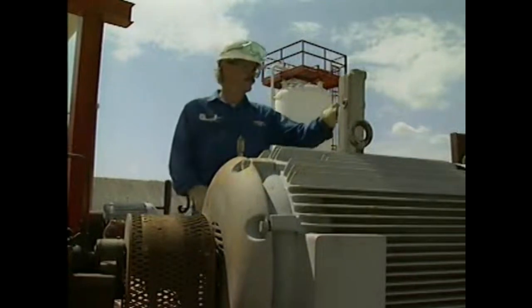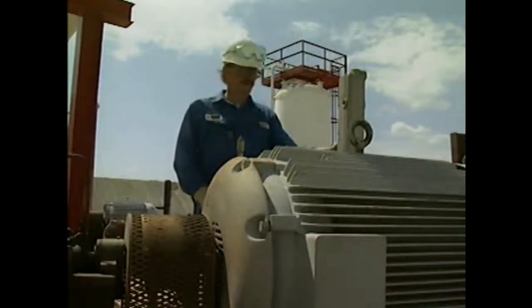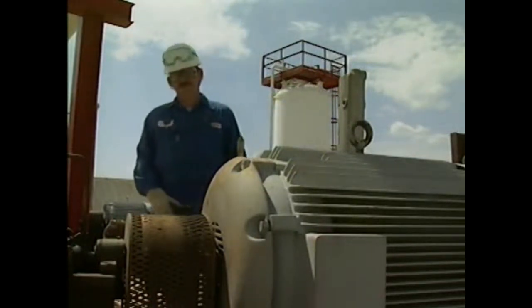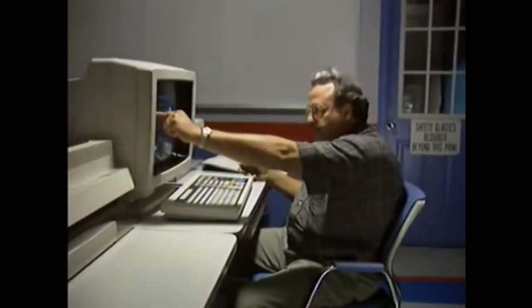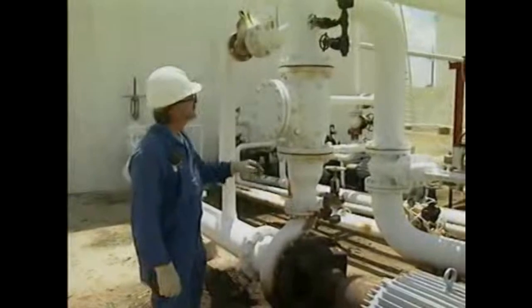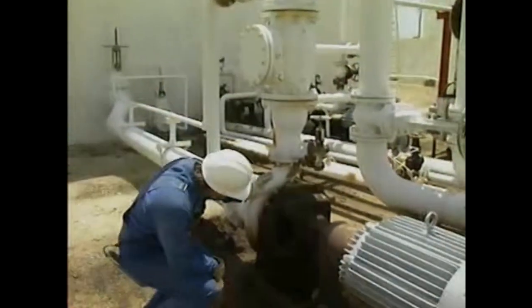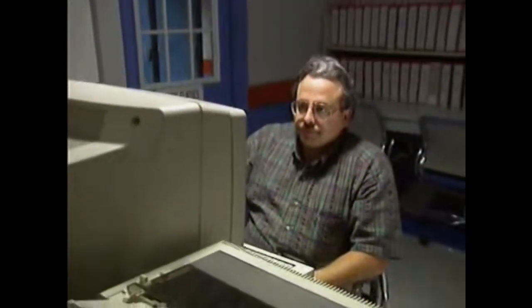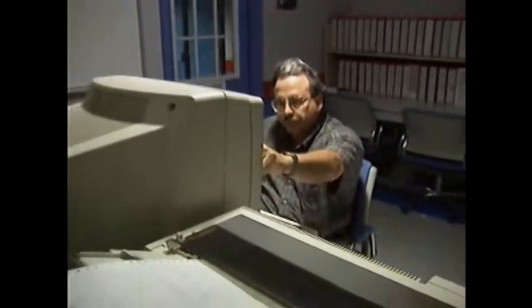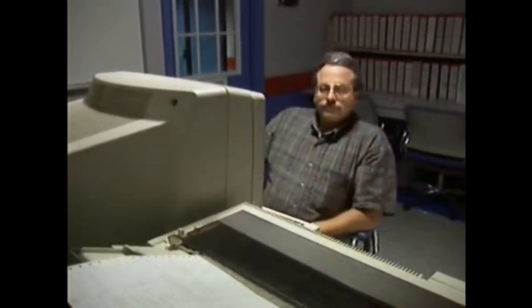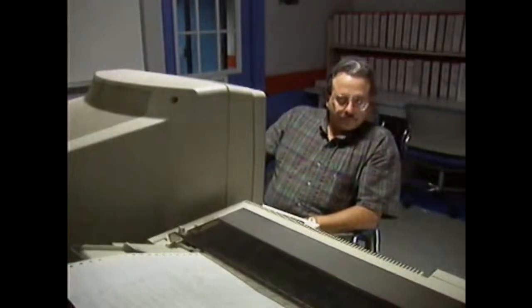After receiving permission from the control room operator, the outside operator starts the transfer pump, while the control room operator checks the appropriate indicators. The outside operator checks the operation of the pump. When the control room operator checks the indicators, he notices that the level in the storage tank is dropping and the level in the process feed tank is rising. Everything appears to be normal.